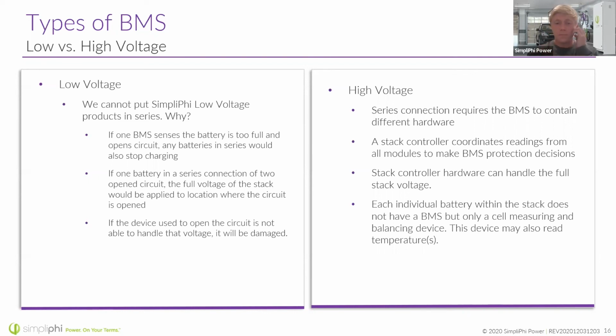If you've got two 50-volt batteries in series, you've got 100 volts, and the BMS opens the circuit and sees 100 volts across that component used to open the circuit, that's going to damage the BMS if it's not able to handle that. So you have to be sure the device used to open the circuit can handle the full voltage. For example, let's say your inverter is charging the batteries at 100 volts. You've got 100 volts going to the battery bank in series, and that BMS, when it opens the circuit, is still going to see that 100 volts right there on both ends of the BMS.